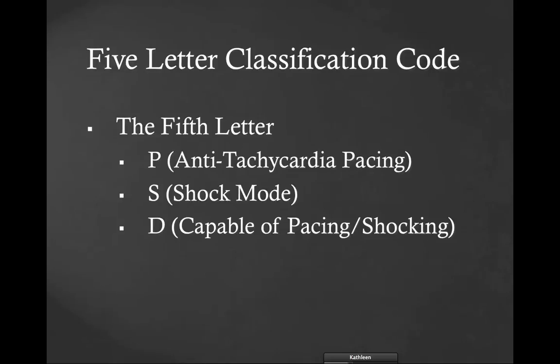The fifth letter applies to pacemakers' design. Is it designed to interrupt tachycardia? Designations can be 0 for no response or P for anti-tachycardic pacing, meaning they override that foci that is causing the heart to pace really, really fast. And that's the ectopic irritable foci that's taking over a very tachycardic response. The anti-tachycardic pacing overrides that in the hopes to stop the tachycardia. That's what a lot of AICD has. They can have this, as well as a shock mode, meaning they shock patients, and they can have D, both capable of pacing and shocking.